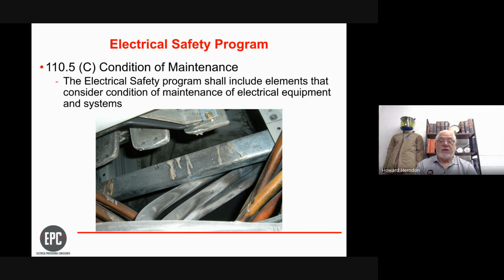When we have an arc flash event like this, we have carbon that's put out by the flash that's in the equipment, and that carbon is not an insulator. It's a conductor. So consequently, we have compromised insulation, and in electrical arenas, that is a huge, huge issue. So condition of maintenance should be considered. Just like when we have a facility and let's say the main breaker or many of the other breakers have not been turned off in many years.